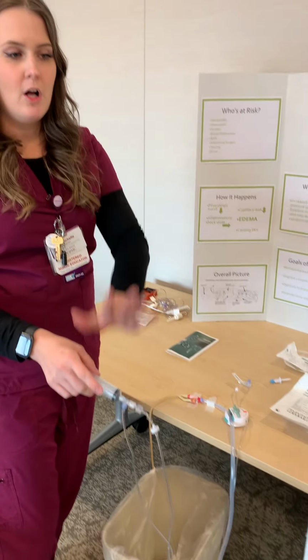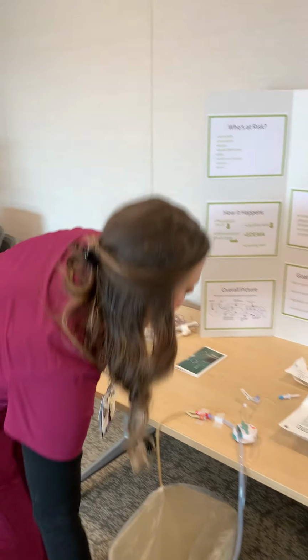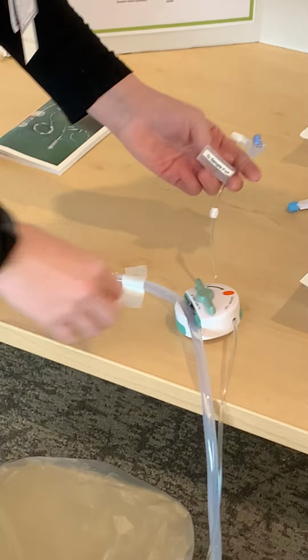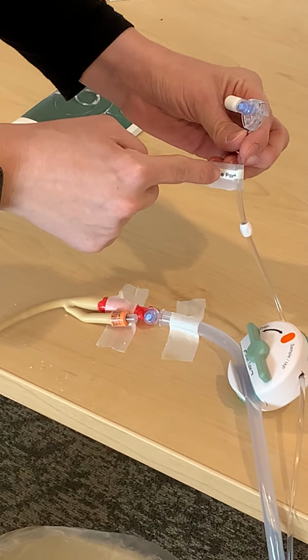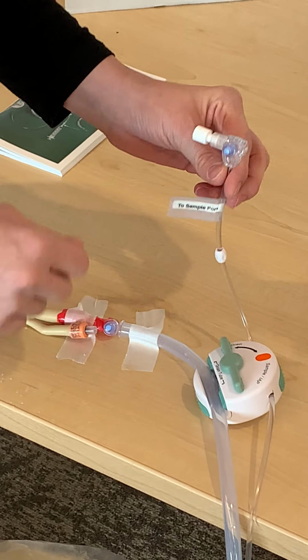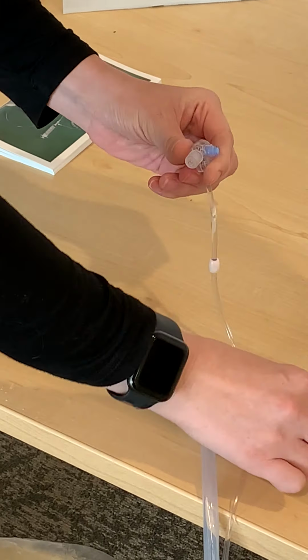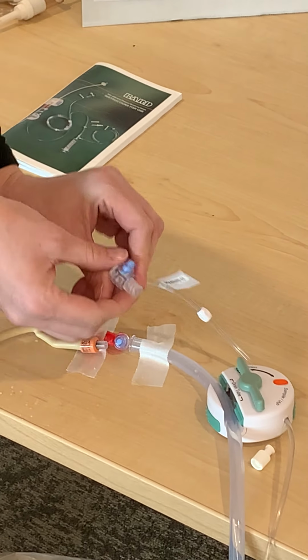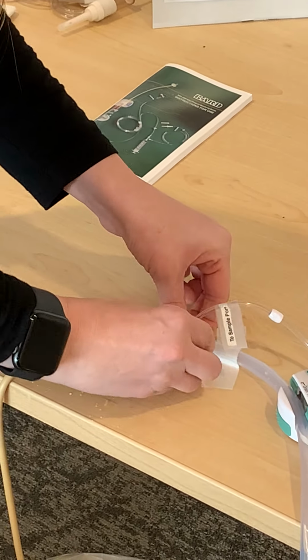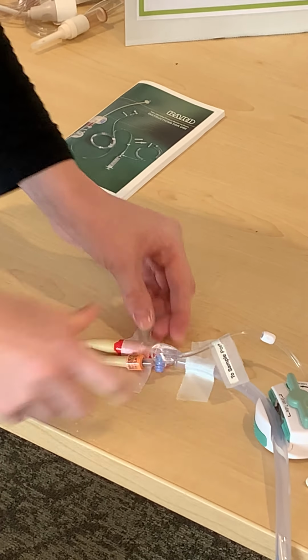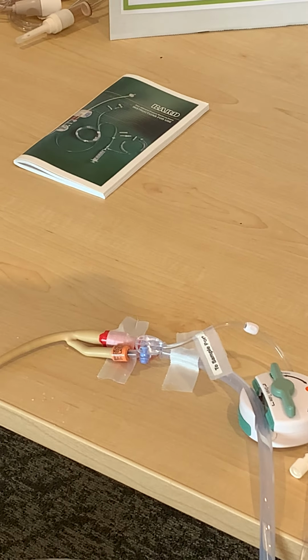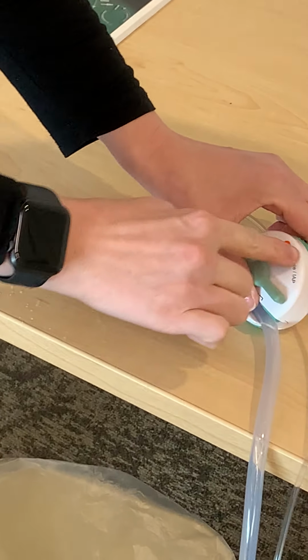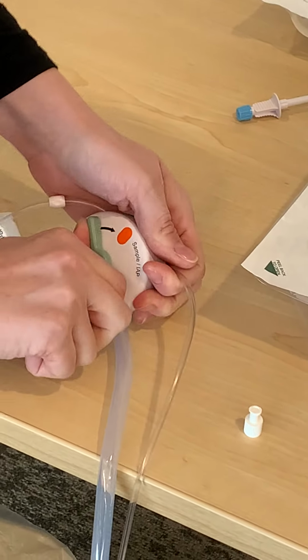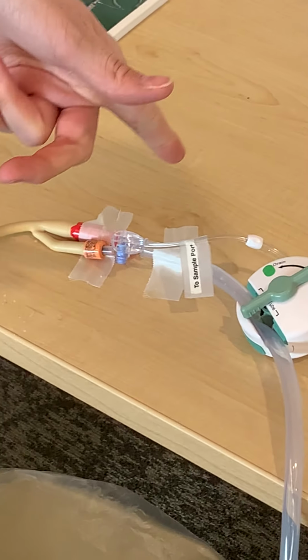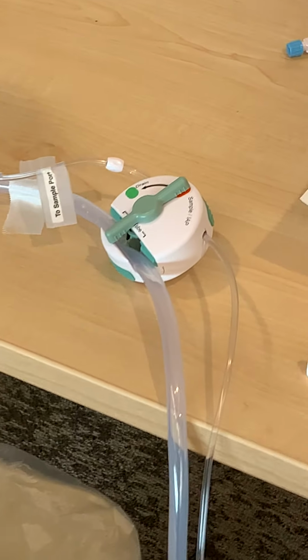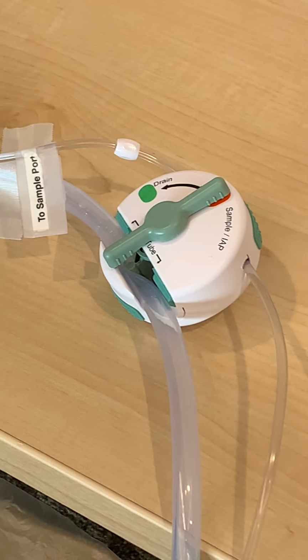So at this point, now that all my tubing is properly primed, this would be the time that you would connect where it says to sample port. I would want to clean this with alcohol. Open this and put it on here. Okay, so I still have a sample port I can collect urine from if I need to, which is why over here it says sample. So we can turn this and either get a sample or do our monitoring. For our purposes, now we're going to talk about the monitoring. How do we do that?